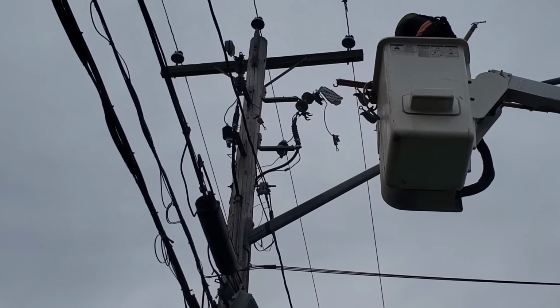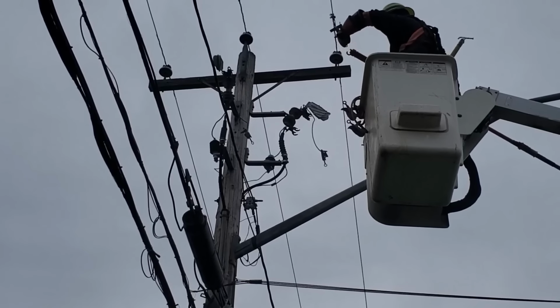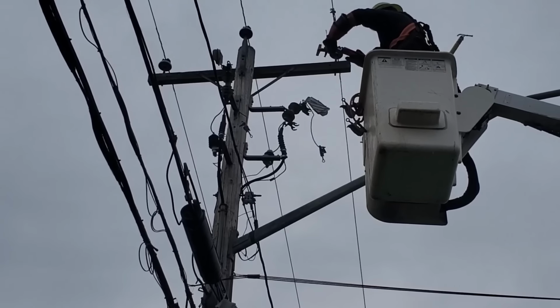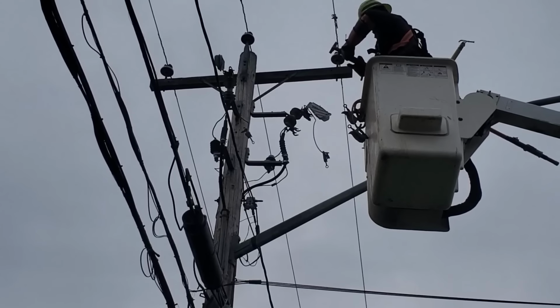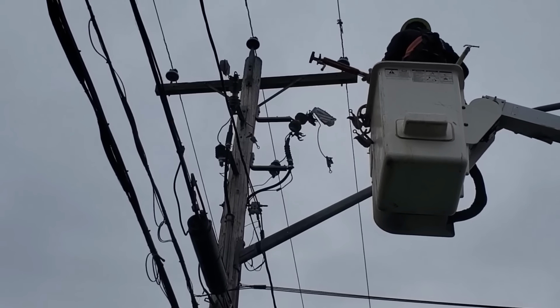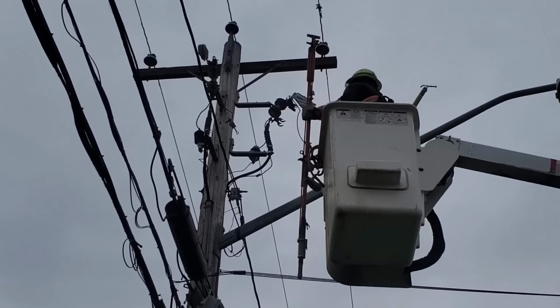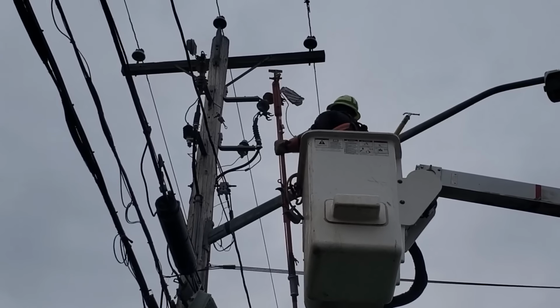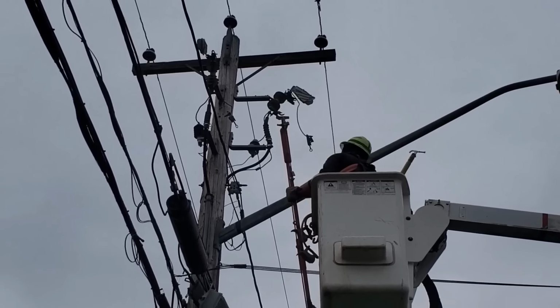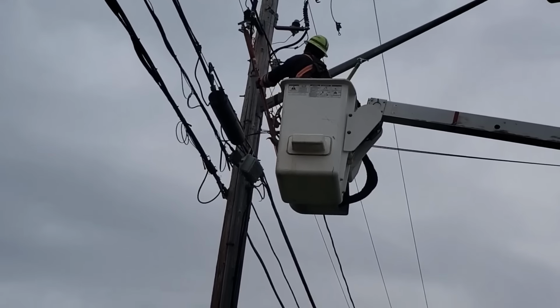Now, when we open a line like this, both of those cables, they go over to the pad mount. That's it. So it's a radial feed. Basically, there's no alternate feed once they're open, so we don't have to check any open points on the other end. In this case, however, where our work area does rely on two protection points, two open devices, we're not taking it as a radial permit, we're taking it as a permit with two protection points.